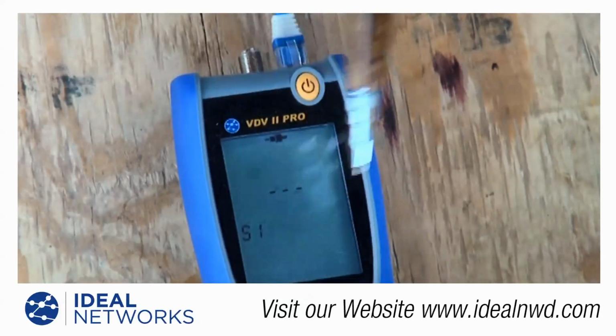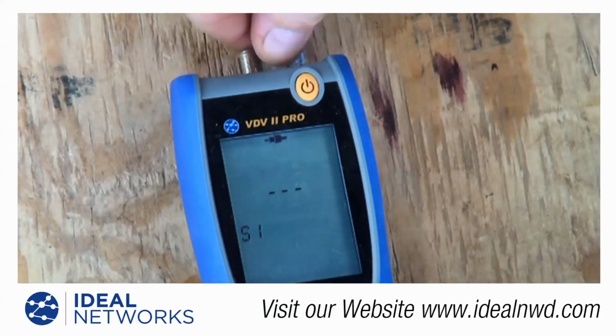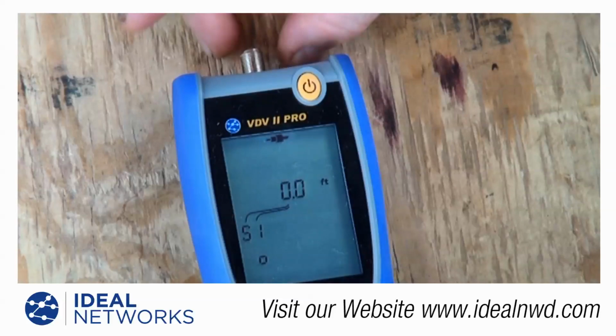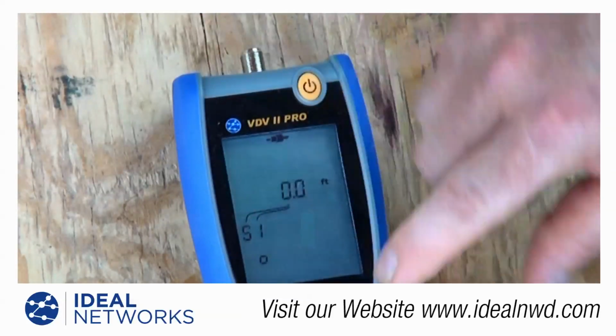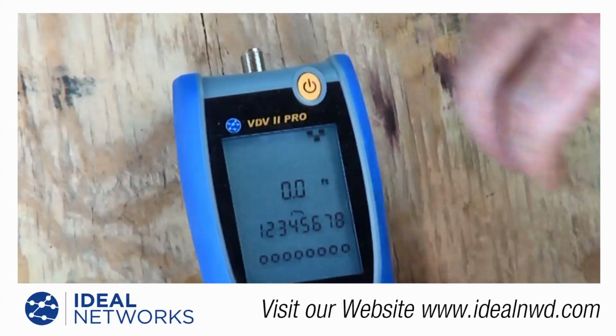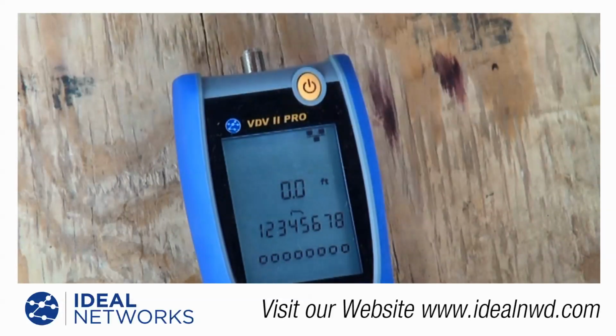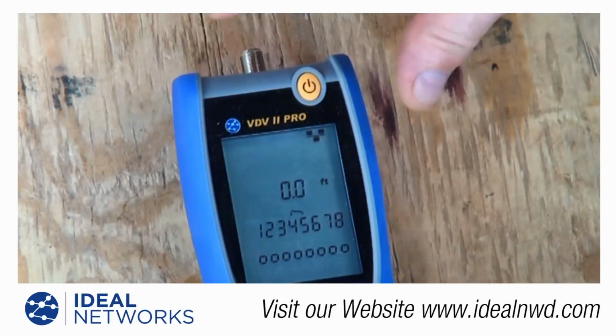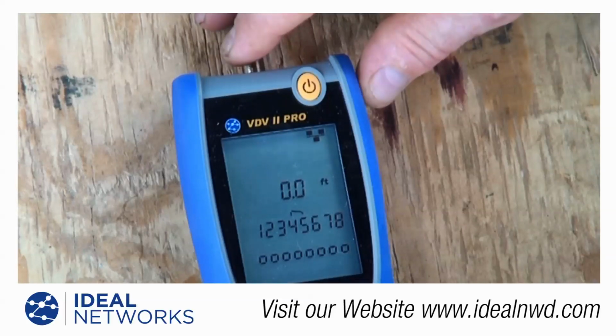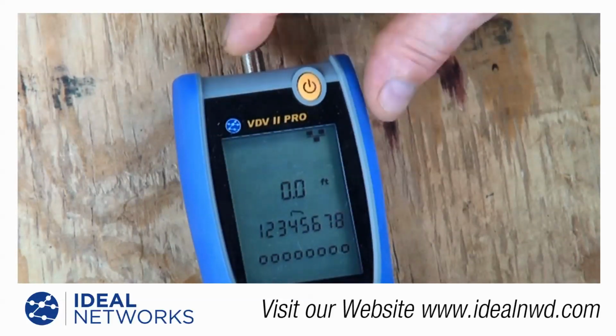But again, it sees something wrong, so it's not right. Make sure you're plugged into the right port when looking at the voltage, and that you have it on the right setting - it eliminates some problems. Being able to identify a voltage present on the end of the cable is very handy when troubleshooting either phone or data circuits out there.